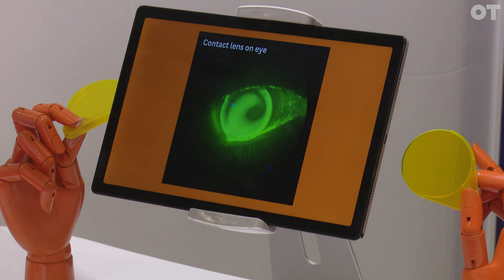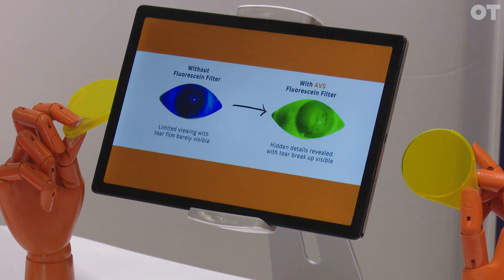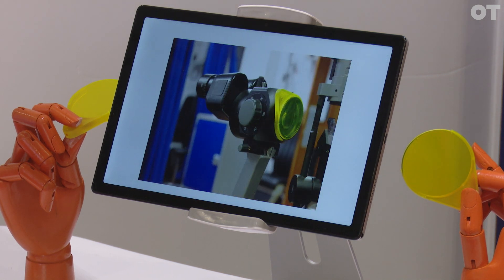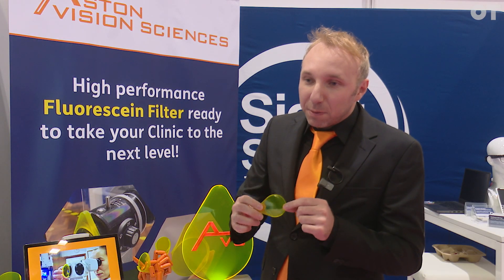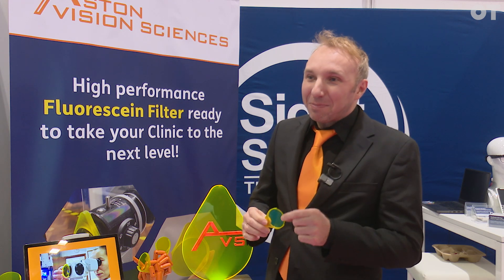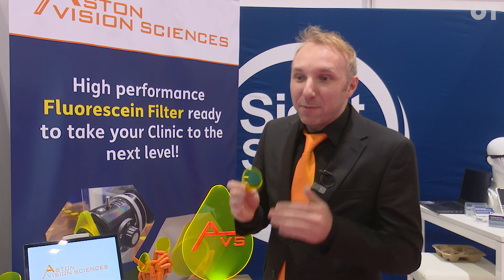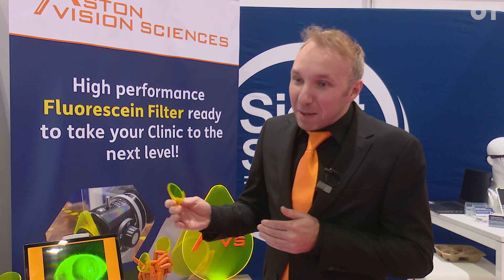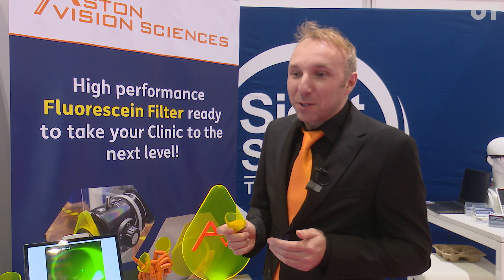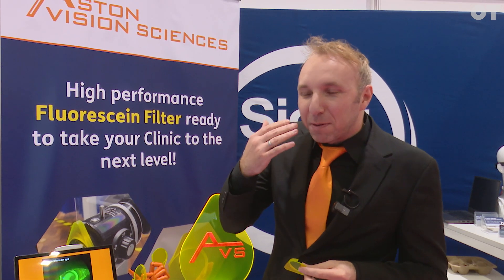I know that a lot of clinicians are very happy with the equipment they have, and that's fine. So what we've done is created a solution that will fit onto most existing slit lamps. It clips onto the front of the objective lens, and if not, it can still be held by hand. What's special about this filter is the colour formula, which I spent years developing as part of my PhD. The colour formula is tuned to be very close to fluorescein emission, meaning you get very high contrast and very high clarity, even at lower blue light levels — which is better for the clinician, so they can see clearly what's going on.